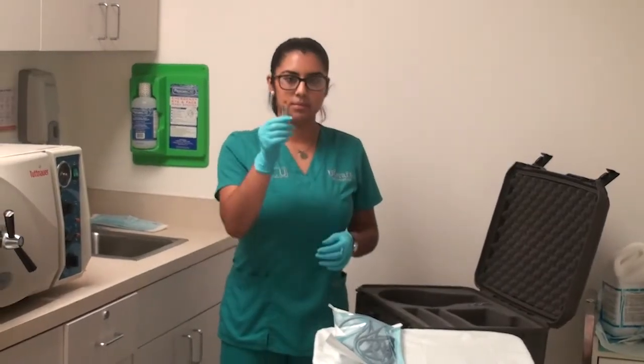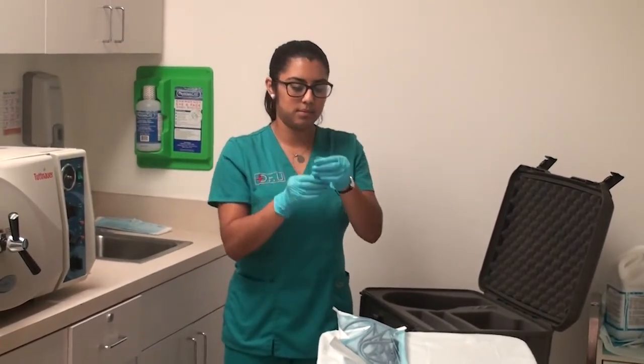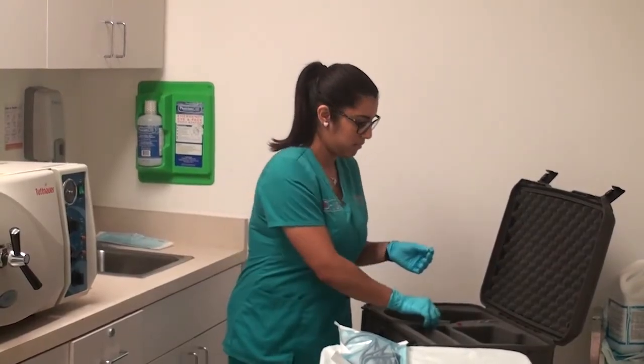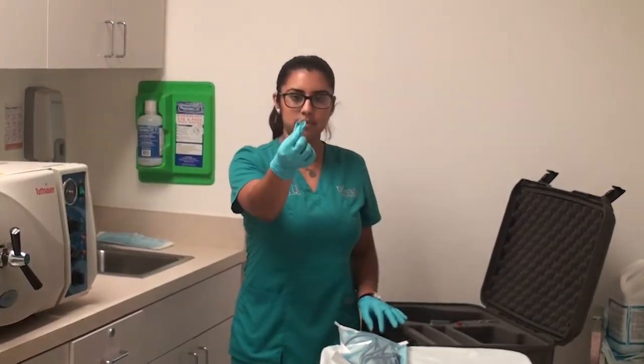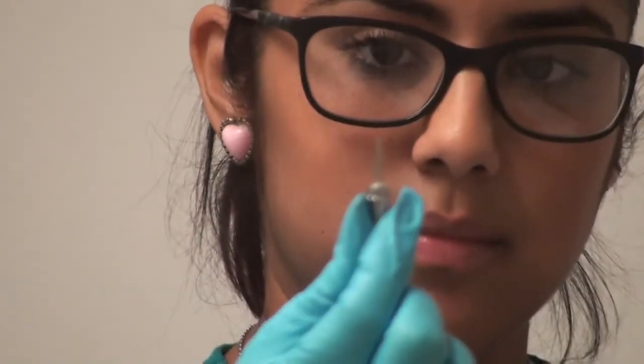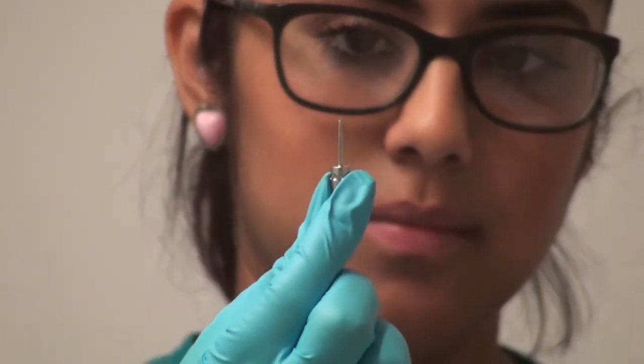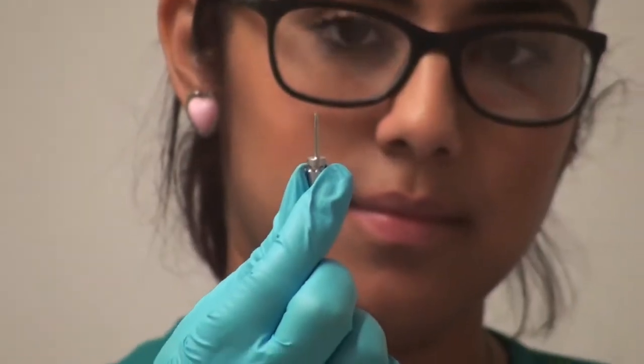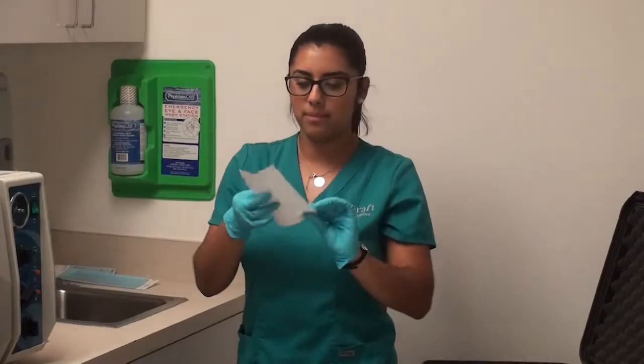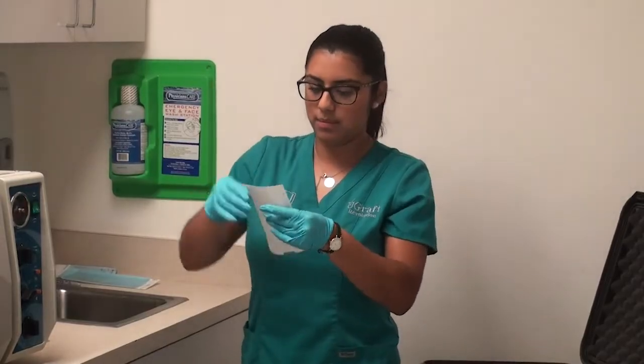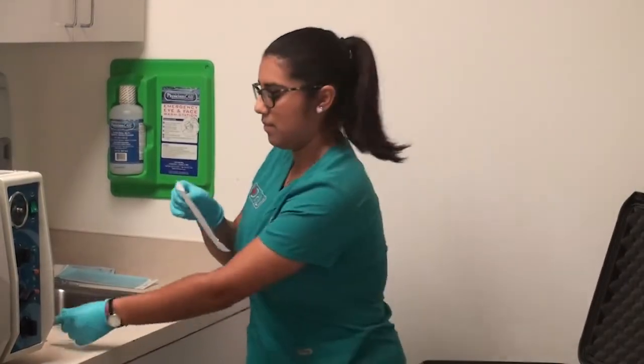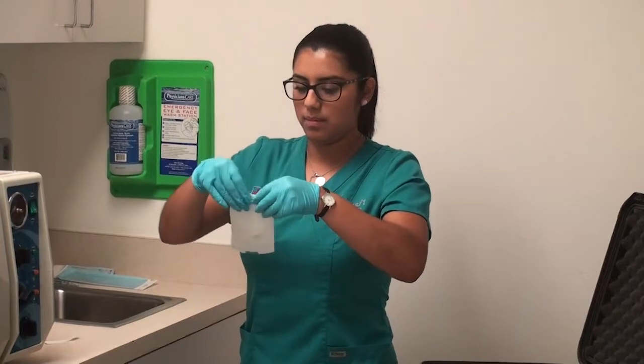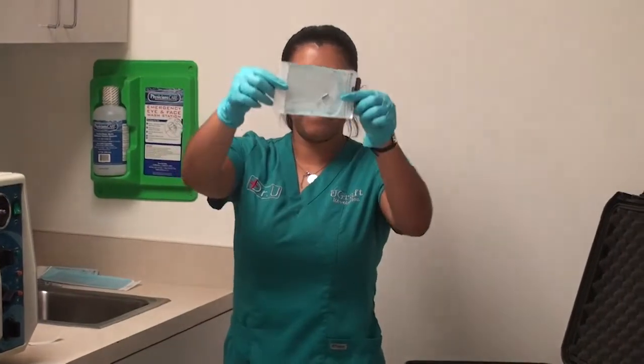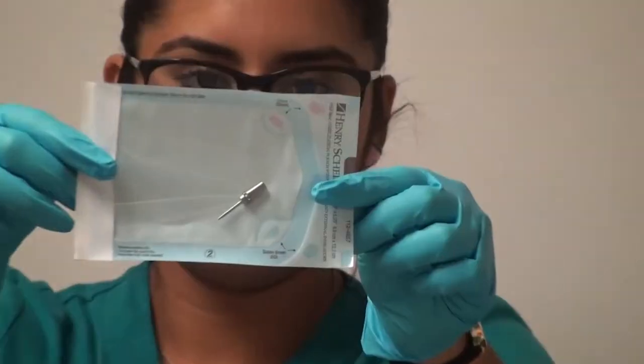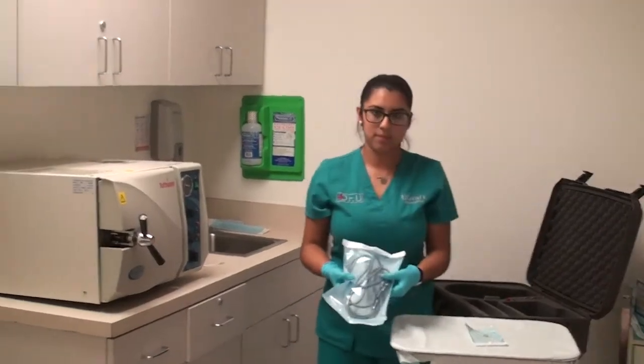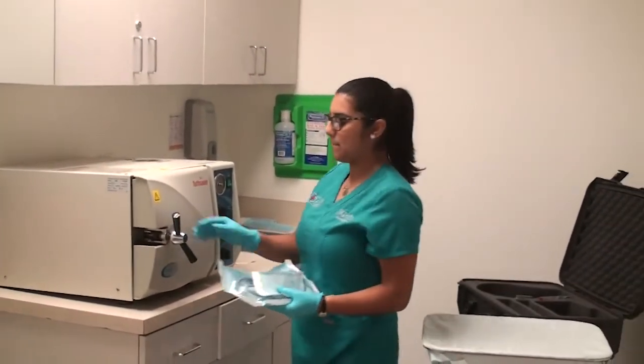Next, you would need to sterilize the intelligent punch. This is the Dr.U Punch I, also called the intelligent punch, which works with the handpiece. This is what it looks like. It arrives unsterilized and must be sterilized before use. You can either sterilize it naked or by first placing it in a sterilization pouch of appropriate size. Then, place both the handpiece and the punch into the autoclave machine.